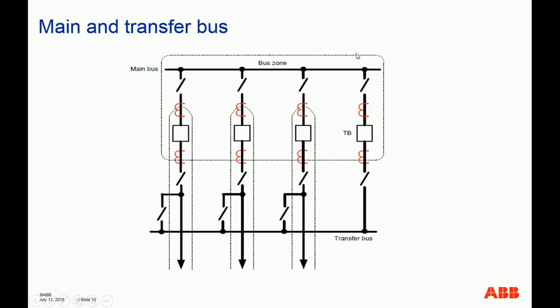For example, for this third breaker, you can close the tie breaker and its disconnects first, so that the tie breaker supplies the load of this feeder. Then you can safely open the breaker and open its disconnects, so that you can put that breaker out of service. So this gives you that extra flexibility.